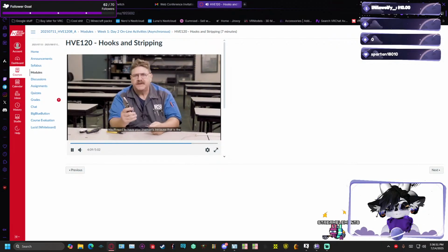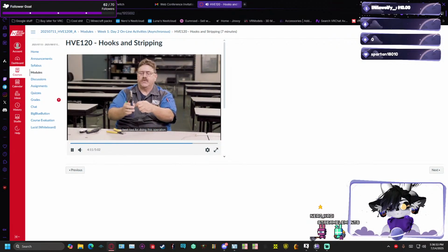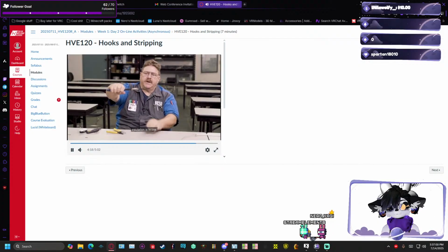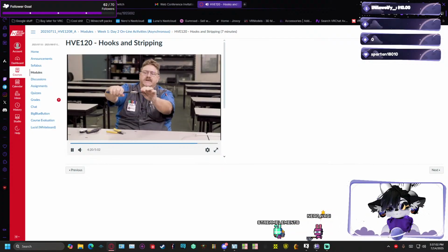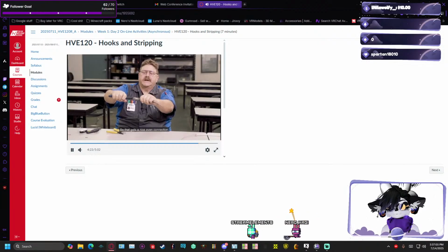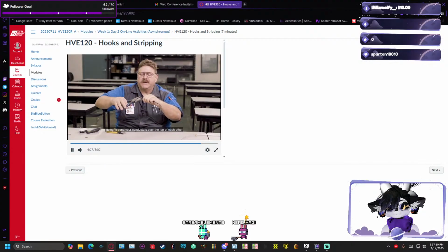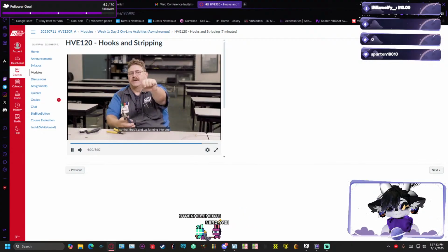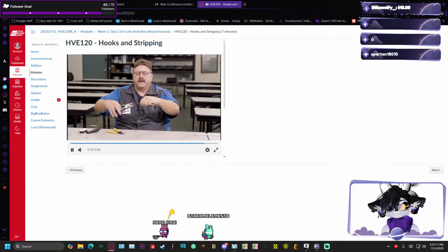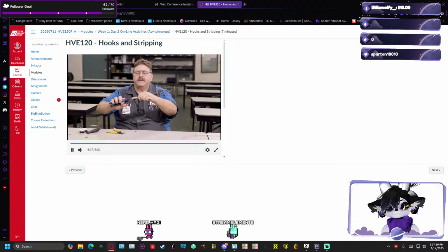You'll need to have your lineman's, because that is the best tool for doing this operation, lineman pliers. You're going to take your 3 conductors, put them together, parallel to one another, making sure your insulation is in line so that it gets a nice even connection when you do your first twist. Your first twist, you're just going to bend your conductors over the top of each other so that they'll end up forming into one another. Then you come back at different angles and pinch them into one another until they form a spiral or a twist.